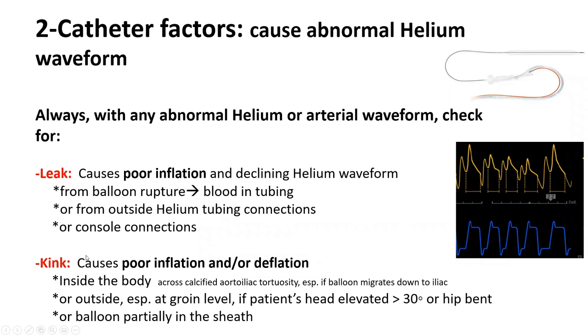The second big problem you see with the balloon pump gas waveform is kink. And kink, depending how bad it is, if it is very severe, will cause poor inflation progressively with cardiac cycle. If it is not too bad, it will allow inflation, but the catheter will kink and collapse further during the sucking of deflation. So you'll end up with a balloon that inflates but doesn't deflate well. So we'll get distortion of that portion of the balloon pump. And I'll show you some pictures. So it can cause either poor inflation, or okay inflation but poor deflation.